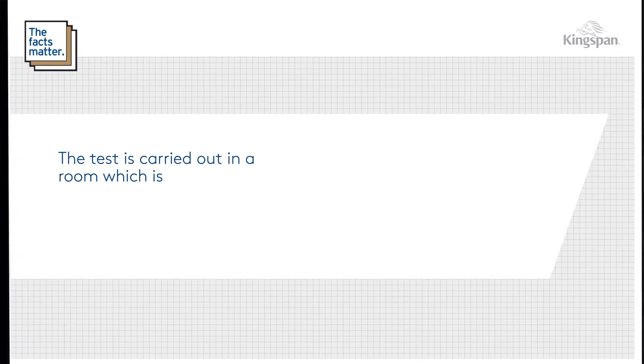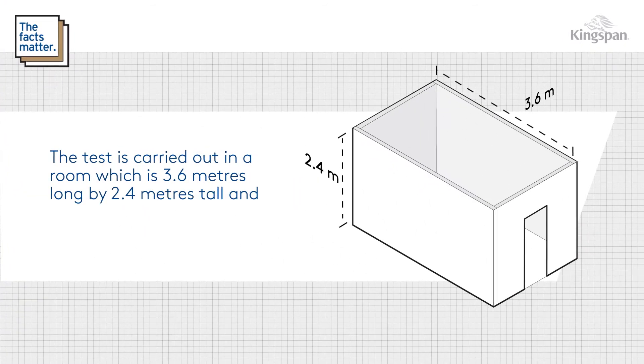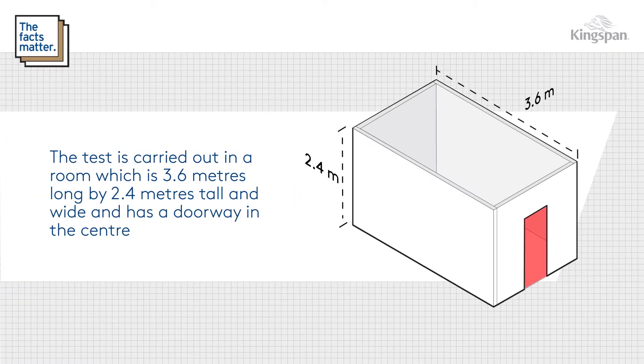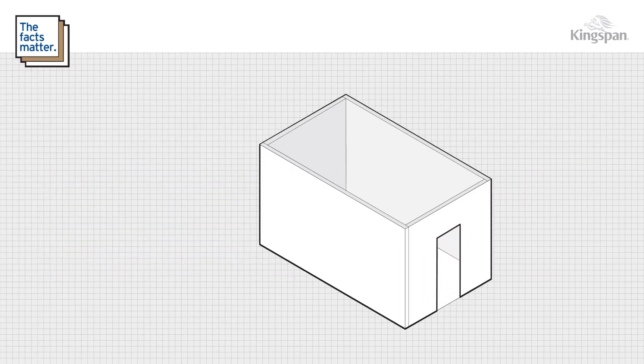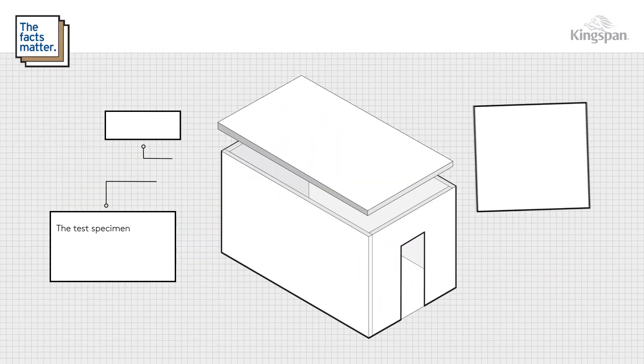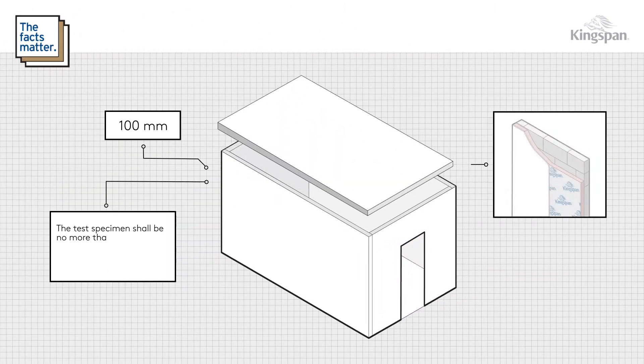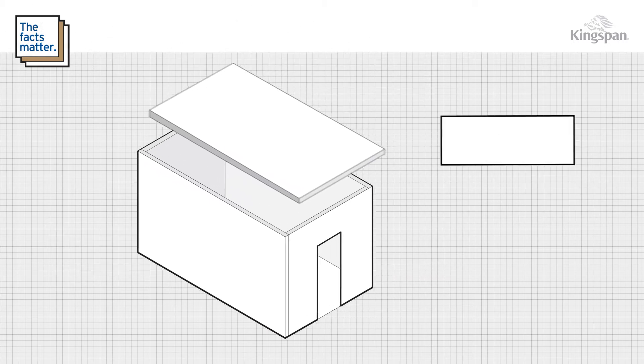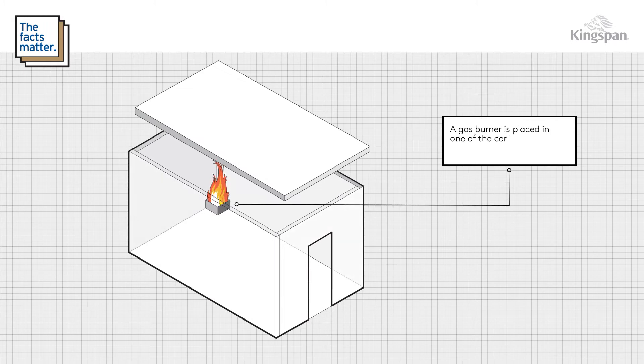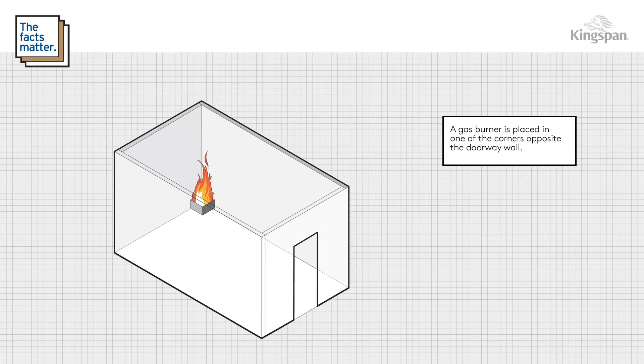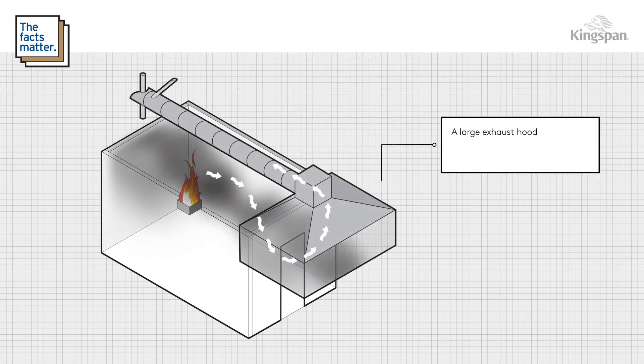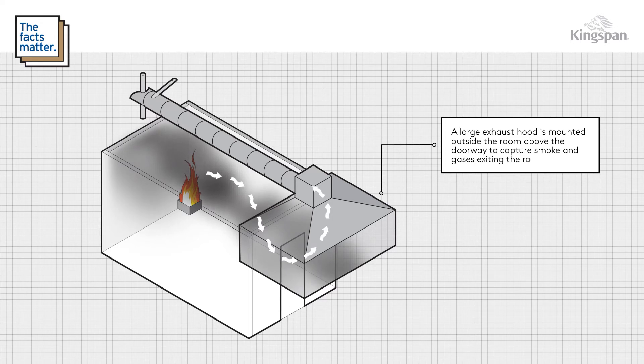The test is carried out in a room which is 3.6 meters long by 2.4 meters tall and wide, and has a doorway in the center of one end. The test specimen shall be no more than 100 millimeters thick, including an air gap, and lines the ceiling and three of the room's walls. A gas burner is placed in one of the corners opposite the doorway wall.